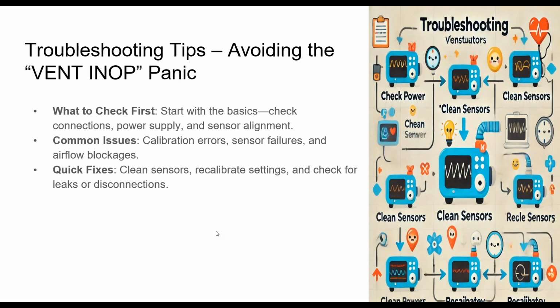The flow sensor at the exhalation side is a good example of this. It gets enough humidity over time, and if it's a heated wire flow sensor, it heats up enough that it burns off some of the wire over time, and its resistance changes. And then there's another common issue, and that's airflow blockages of some type. This will typically get resolved by the respiratory therapist, but you may be the first call, or you may be called almost right after the respiratory therapist because the nursing staff has observed this problem and they need somebody there now.